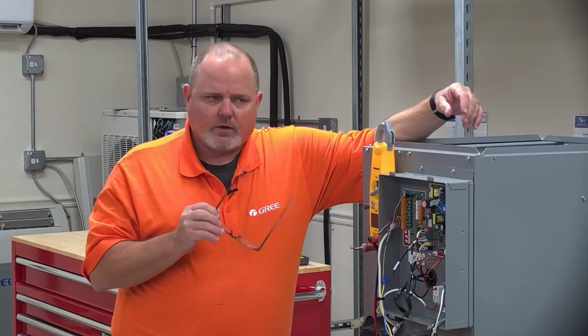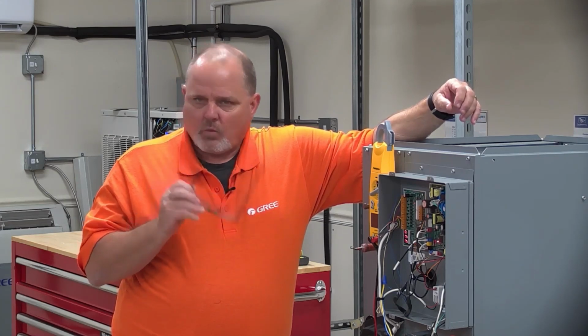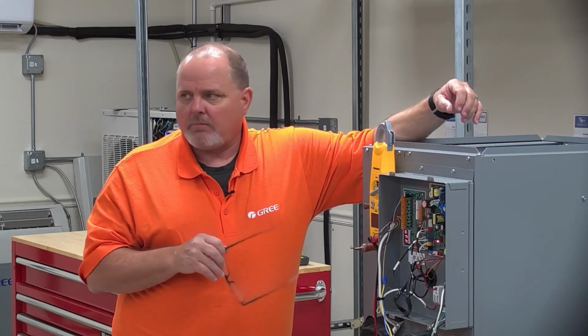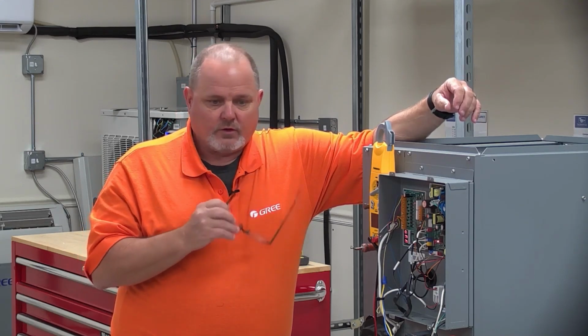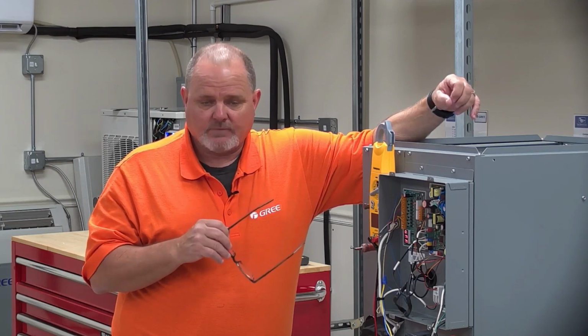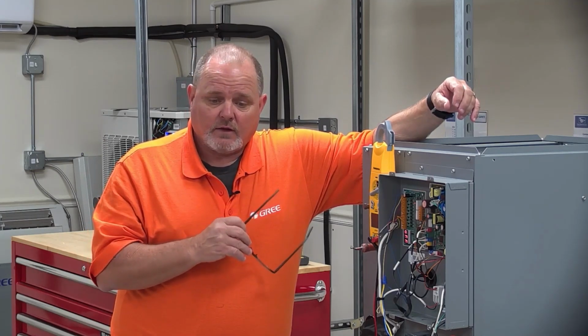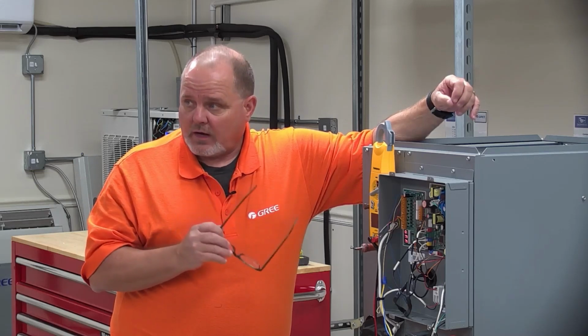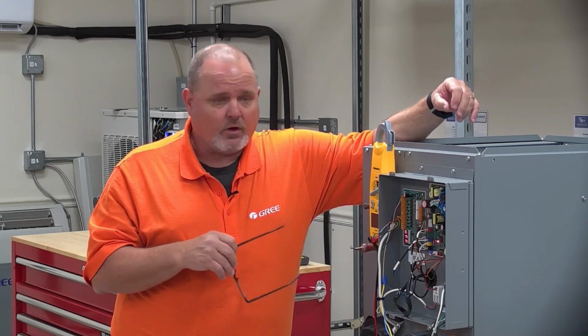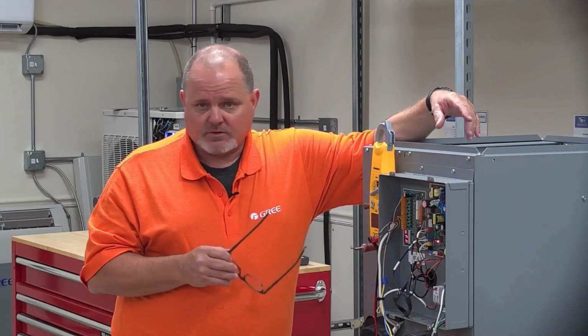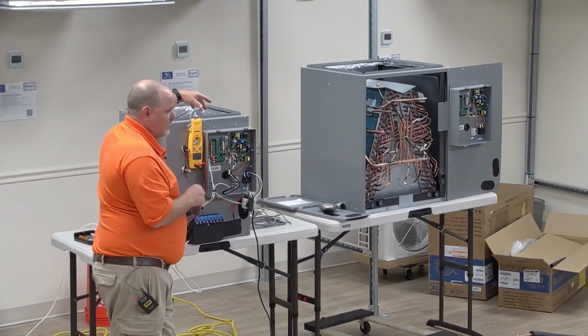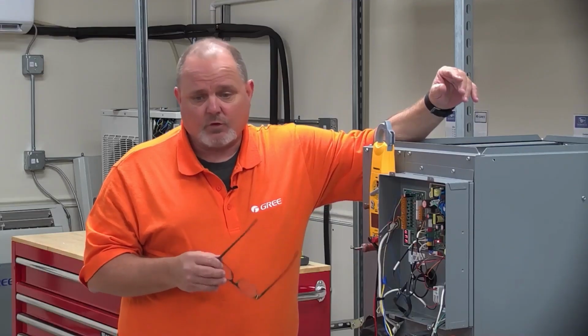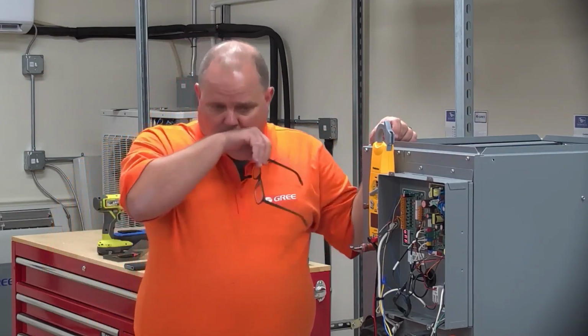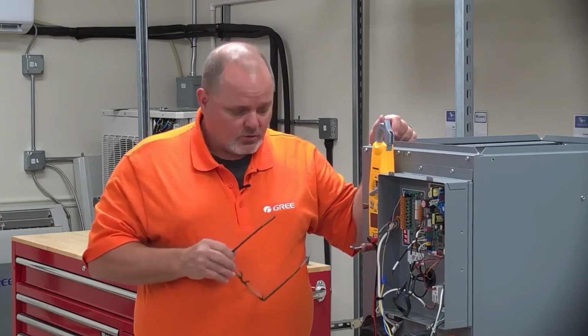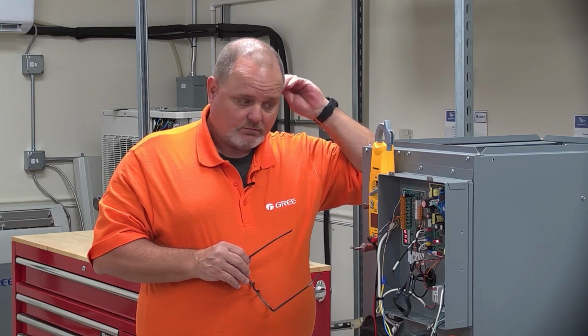Soon, in one of our live broadcasts, we will have this dual fuel coil set up on a gas furnace along with the new MultiPRO Ultra, the GMV6 version, and we're going to do a wall mount with that, and we're going to do an air handler with that. And then we're going to have another training with it all functional, and you guys will actually be able to see it in operation with it running and be able to switch it over like as if it got a gas heat call. Now, I'm not going to put gas heat to it or fuel to it. I'll have fuel in this building, but I am going to get this all functional up and running for you guys so you can see how to do it.